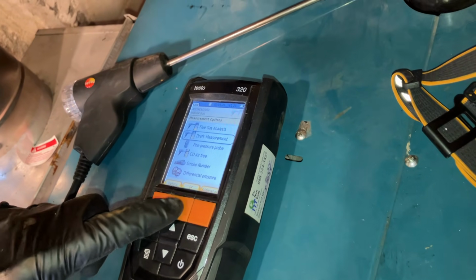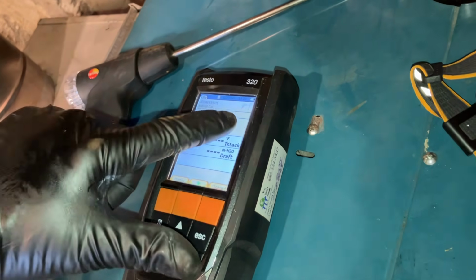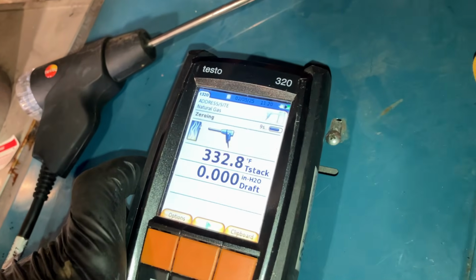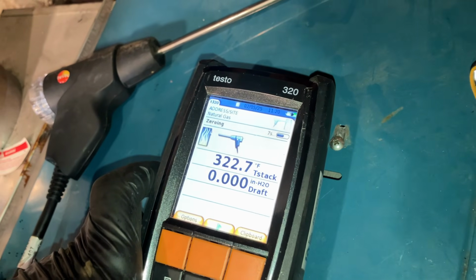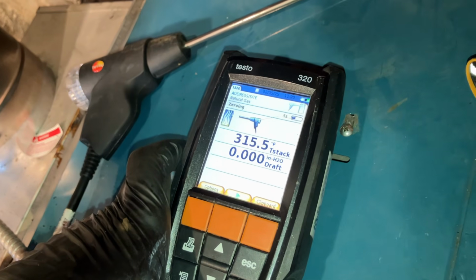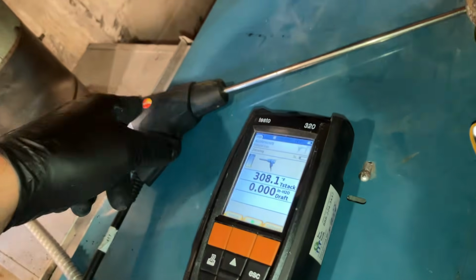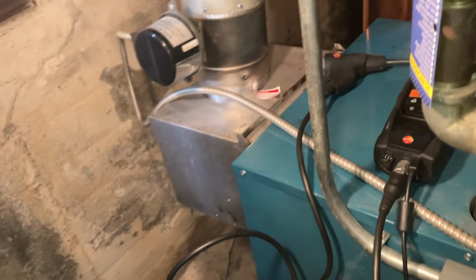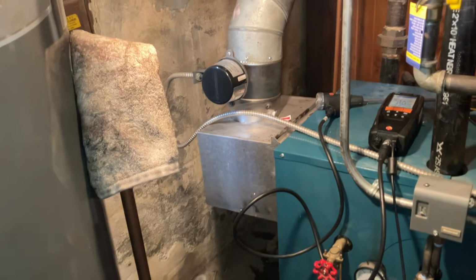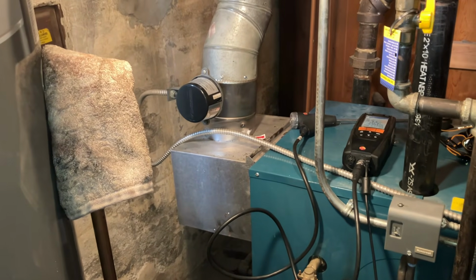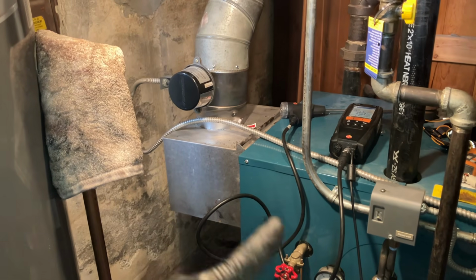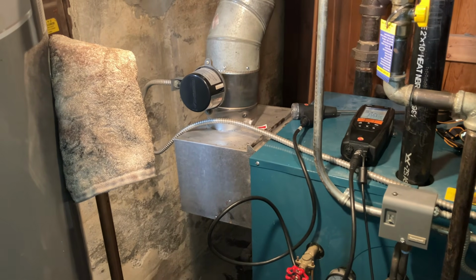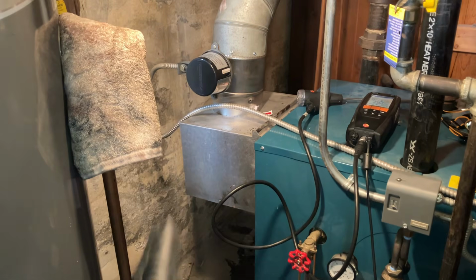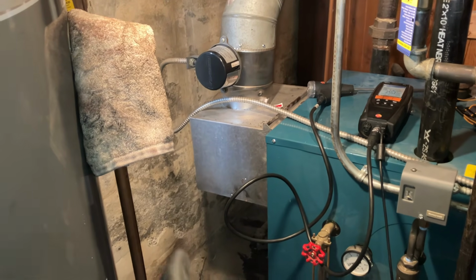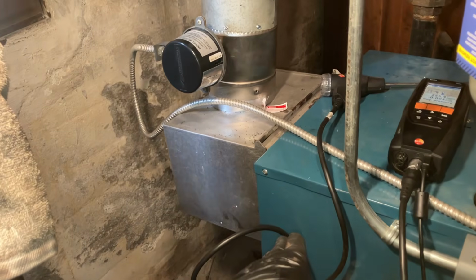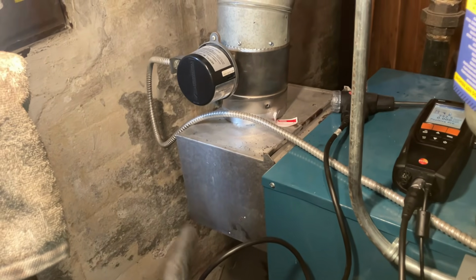We're going to go to draft measurement. It's going to zero out for 11 seconds. Your combustion analyzer may be different, but my Testo 320 zeroes out for 11 seconds. Make sure the probe is not in there. Now, I am going to test for draft at the same exact location where we did our combustion flue gas analysis. There are some going to say, Mikey Pipes, that's the wrong location. What I'm about to do is how I was instructed about 20 years ago.